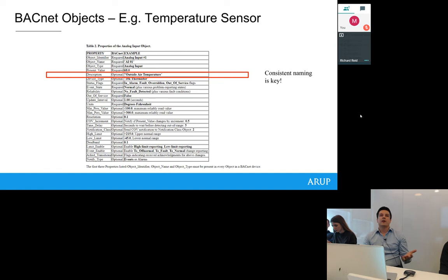So in this case, it's outside air temperature. When I go into buildings and suck up all the data from the buildings, whether that's temperature sensors or valves, some are called temperature sensor, some are called temp sense, some are called TS, some are called TWX. How do I know I've got all of the temperature sensors in the building and all the information that I need? So this is where we need a consistent naming.